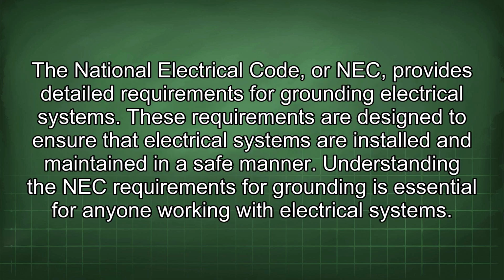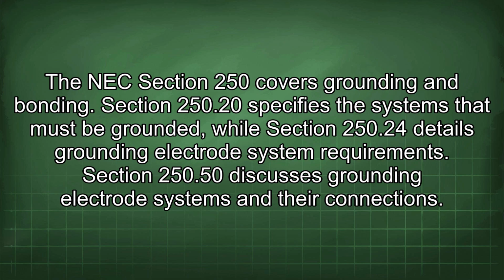The National Electrical Code, or NEC, provides detailed requirements for grounding electrical systems. These requirements are designed to ensure that electrical systems are installed and maintained in a safe manner. Understanding the NEC requirements for grounding is essential for anyone working with electrical systems. The NEC Section 250 covers grounding and bonding. Section 250.20 specifies the systems that must be grounded, while Section 250.24 details grounding electrode system requirements. Section 250.50 discusses grounding electrode systems and their connections.